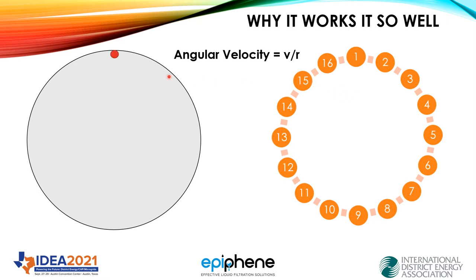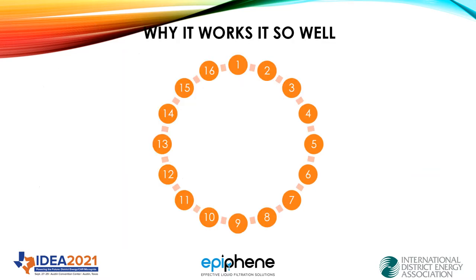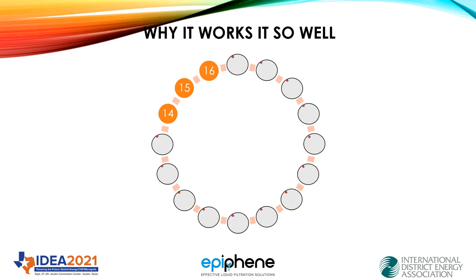Let's replace that arrow with a solids particle. Here's the velocity going around a larger diameter hydrocyclone or centrifugal separator, and let's do the same thing on ours. Notice the difference in velocity and also the size of the particle — basically you're looking at a significantly higher centrifugal action, and that means you're going to have higher efficiency in removal of solids, smaller and lighter. So with our 16 hydrocyclones radially placed inside our vessel, all 16 operating at the same time, I've got the same surface areas providing water to the system, but I'm performing the separation on far, far smaller diameter hydrocyclones, which leads to far greater efficiencies.